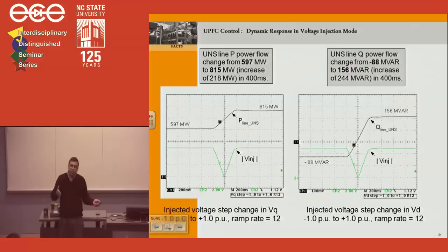The stiffness of the bus, we actually have a number. We call it short circuit MVA. It shows how stiff the bus is to any change. And that number is 18,000. So that means something to us.